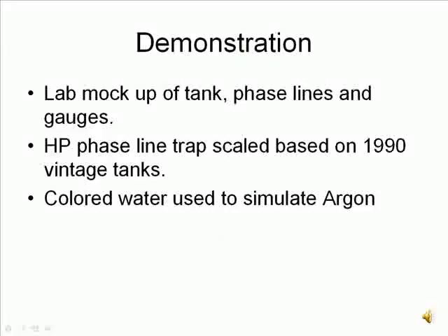We mocked up a test fixture in the lab to demonstrate the drift due to compressing the gas space in the high phase line. Our mock-up used a high phase line to scale based on a 1990 vintage tank. The fluid was water with blue food coloring.